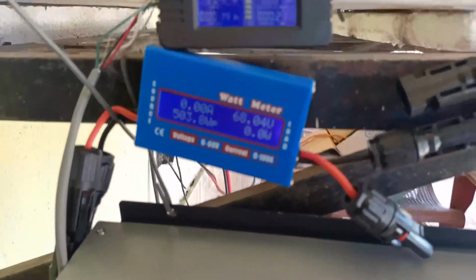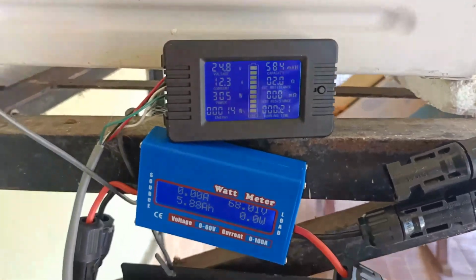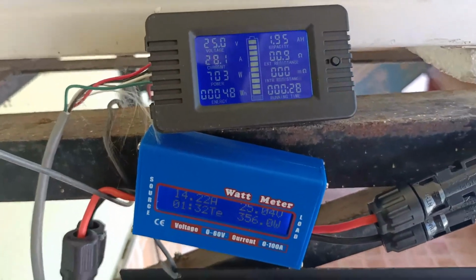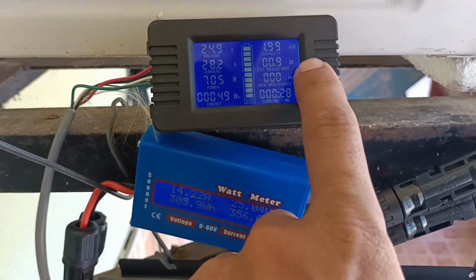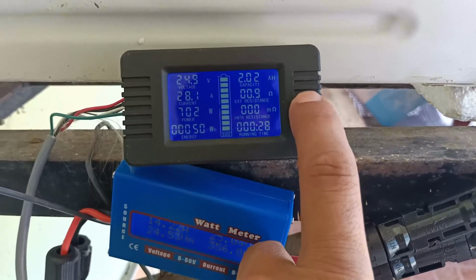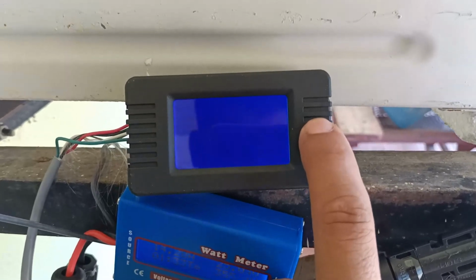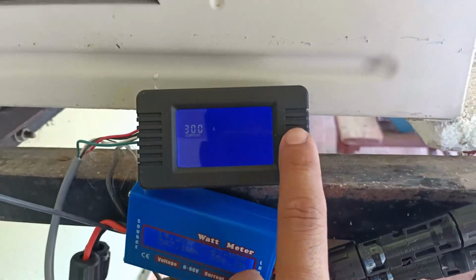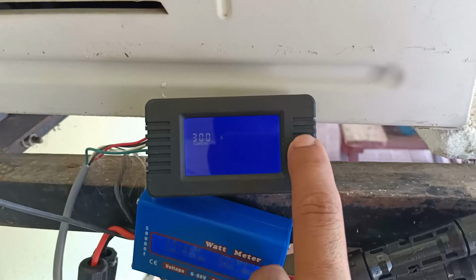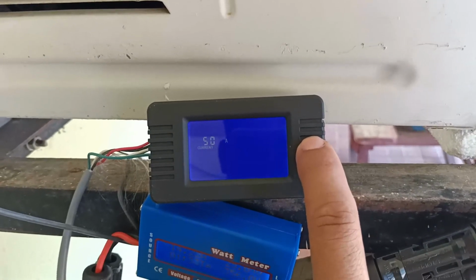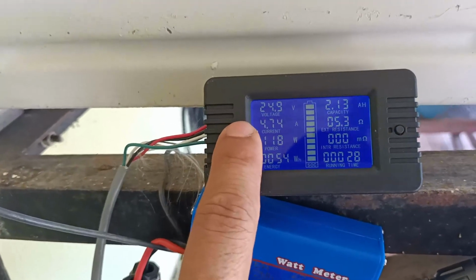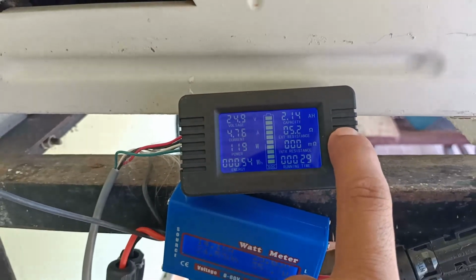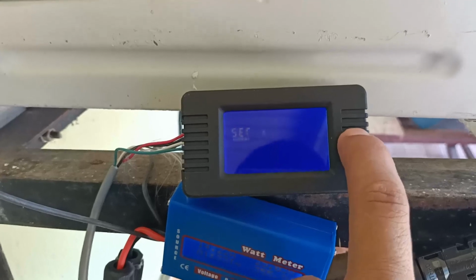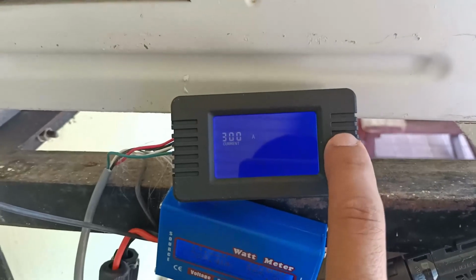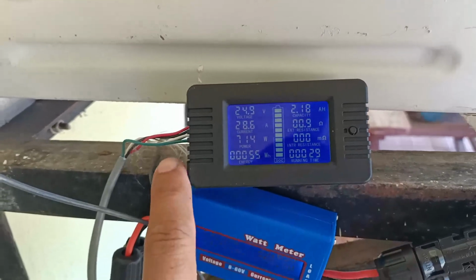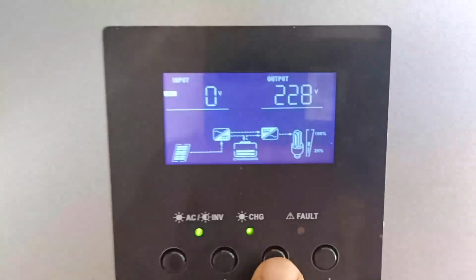So it's not accurate. The device is actually working. I have to set it properly. So to set it properly, long press, and then set the current. It was set to some other value, not 300. For example, if I set it to 50, long press, then that current is wrong. So it's actually working. So what it needs is to set the 50 to 300, and that will match with the current here.